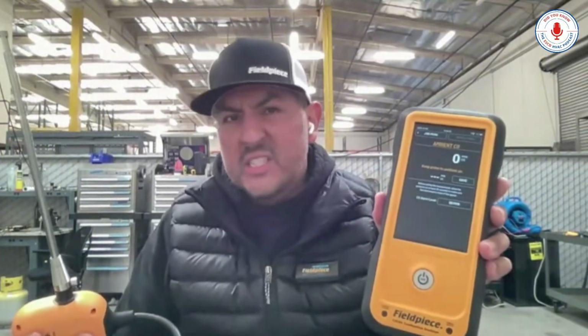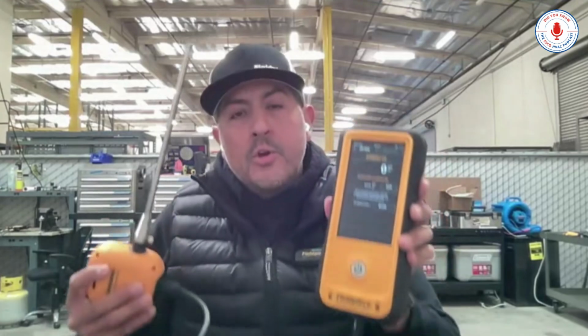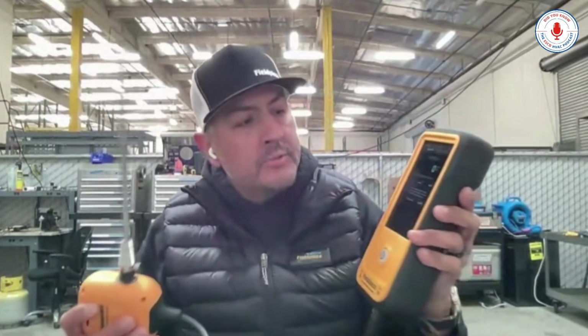If you stay at zero or just get a tick, one or two, there really isn't much to be concerned about. However, if you're walking through a home and you're getting into the teens, 20s, and 30s, then that's something you're probably going to want to stop what you're doing and investigate. And if it's high enough, you're going to want to open up some windows, open up some doors, and start ventilating the area. But step number two, you can perform this test as you're walking towards the appliance under test. Okay. So that's something that you can do. You can save the results of that test by pressing the save button, and all this can be included in your combustion report at the end of the job.